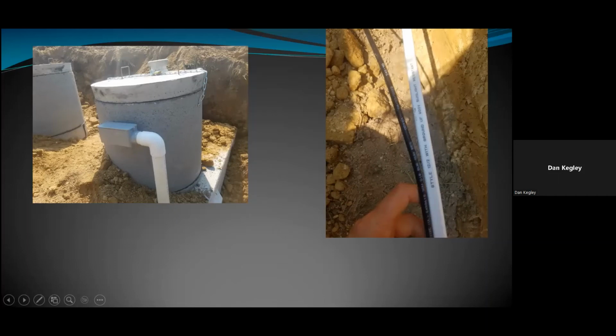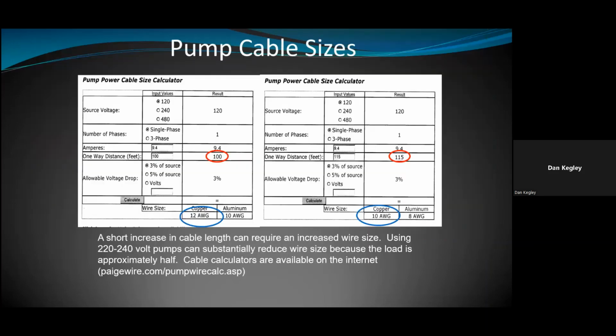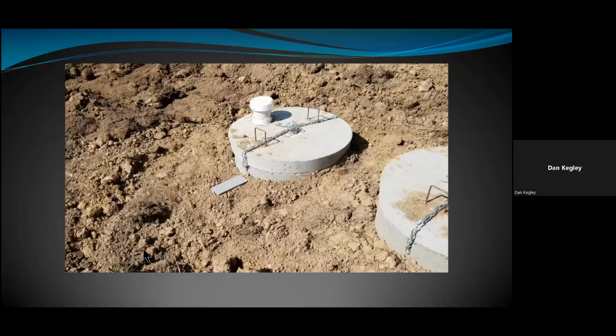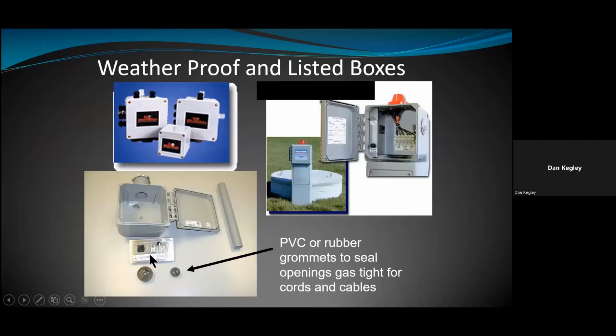Now, if you're terminating, that's a different story. If you're terminating, you have to have those terminations separated with a separator. So the cable itself can pass through and be in the same case, but if you're terminating, your terminations have to be separated. If you're going to be splicing in the same junction box, then you have to have a low voltage splicing compartment and a line voltage splicing compartment. You'll see that some boxes have sleeves put in them. Sometimes, if we go back up to this one here, they'll have these terminals, with the high voltage on the back side of this plate. So this plate is separating the two.